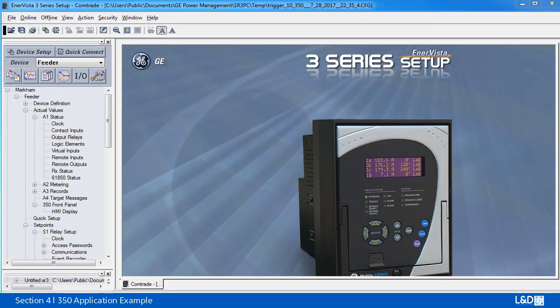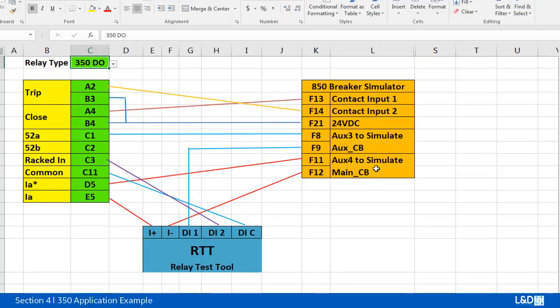Before configuring the 350 auto-reclose function, we need to do the wiring between the 350 and the 850. There's a wiring diagram in the tools provided in the 3 series program. It tells how to wire the 350 relay to the 850 breaker simulator. Depending on the type of 350 relay, we have non-drawout and drawout types. In this demo, I'm using the drawout type, so I choose the drawout type relay and wire the relay from the 350: trip, close, 52a and b, and AC current input connecting through the RTT test set to the 850 breaker simulator.